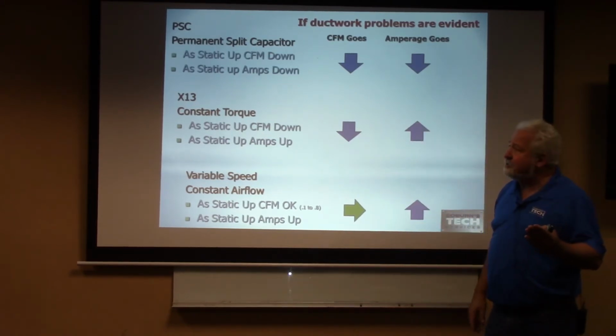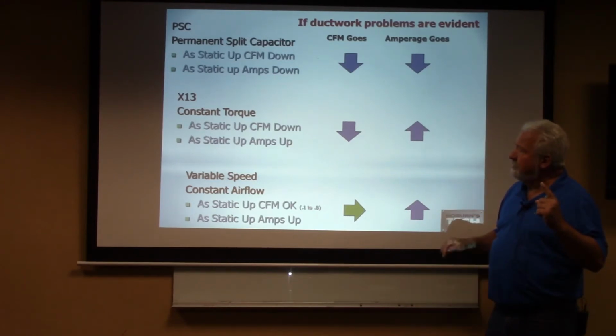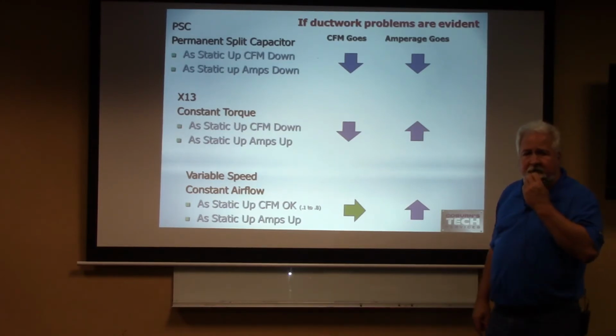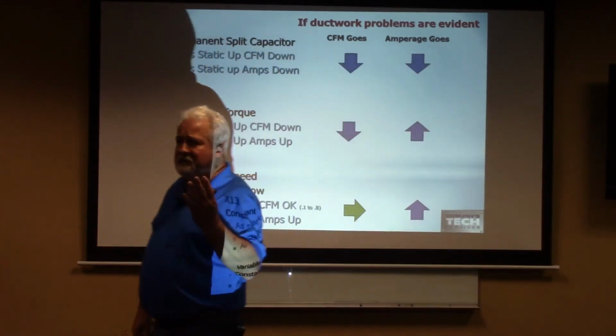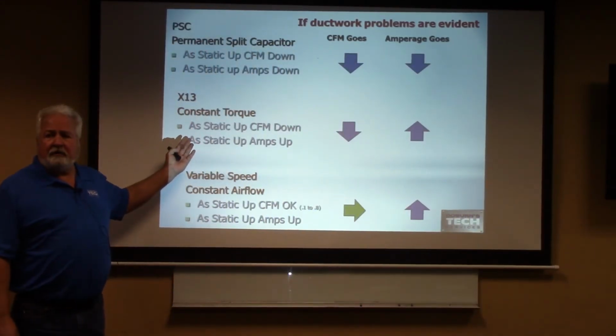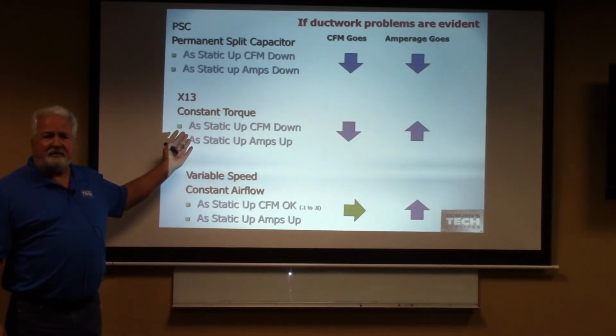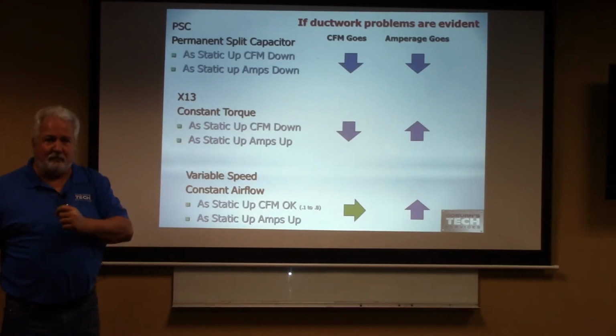Constant torque motors, that's that X13 motor. As the static goes up, the CFM goes down. Static goes up, CFM down. As static goes up, the amperage goes up. Okay. So wait a second. When I put these X13s on that bad duct system, what's happening to the CFM? Goes down. What happened to the amperage? The amperage just went up. Now I'm going to burn up the motor.